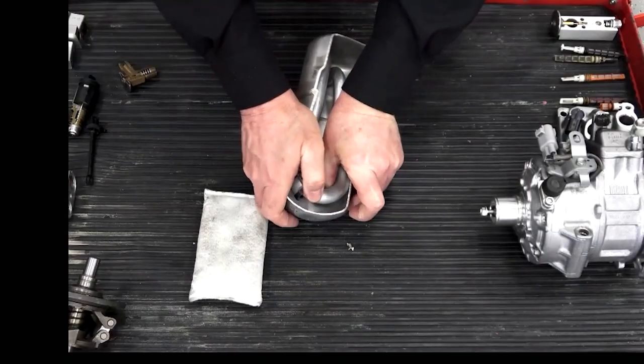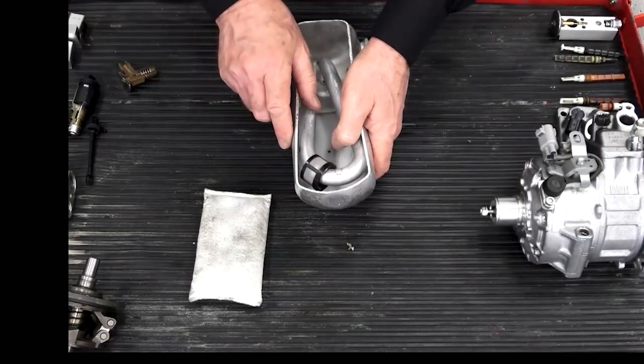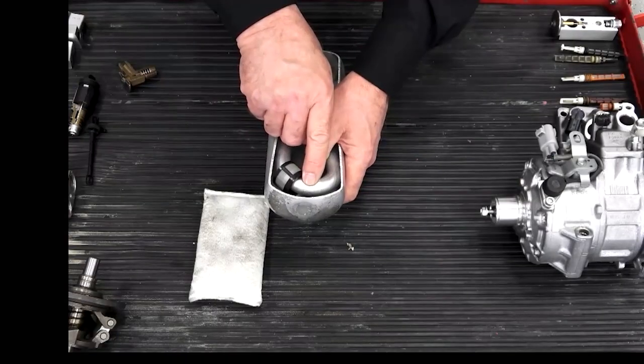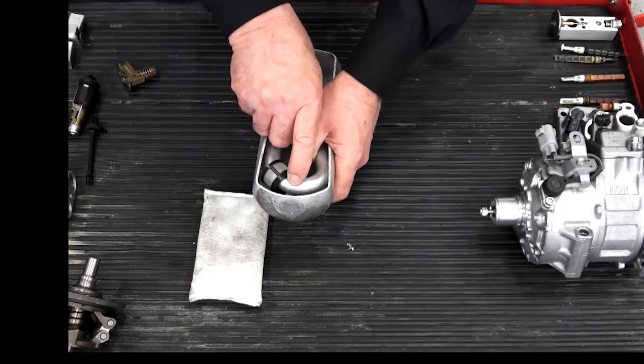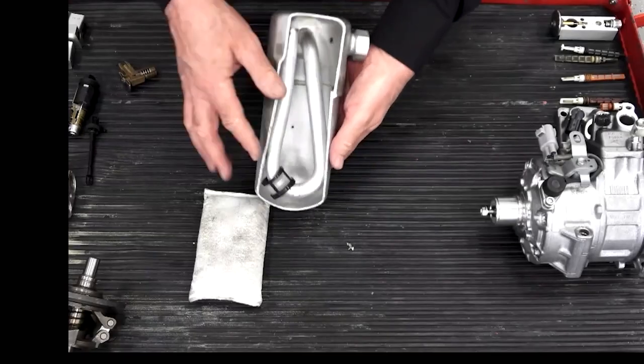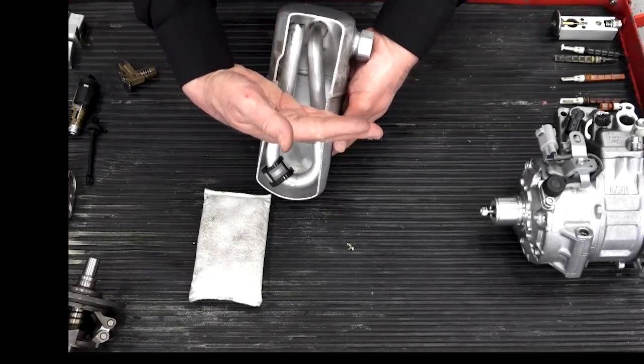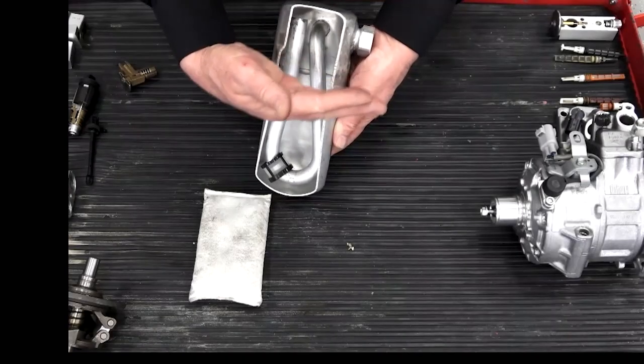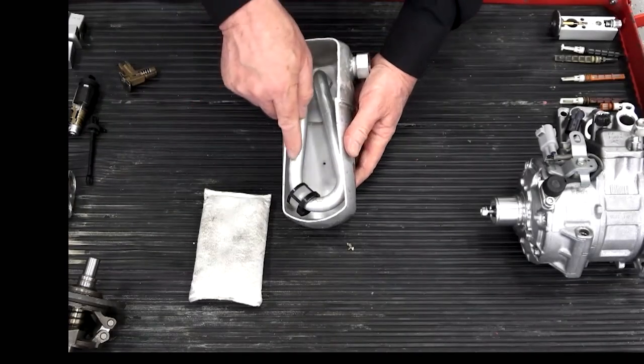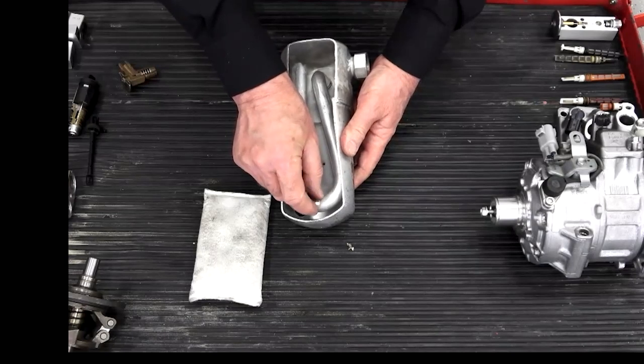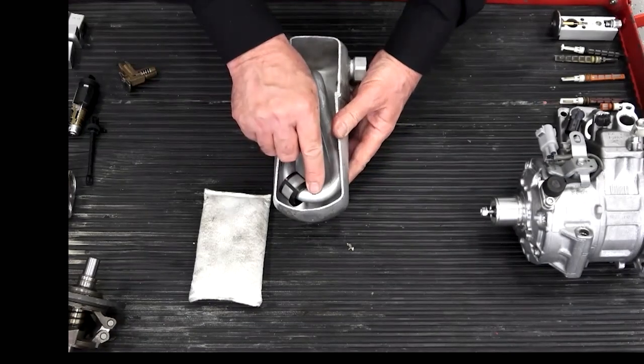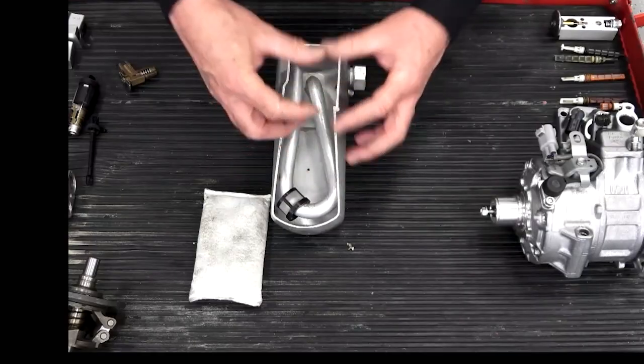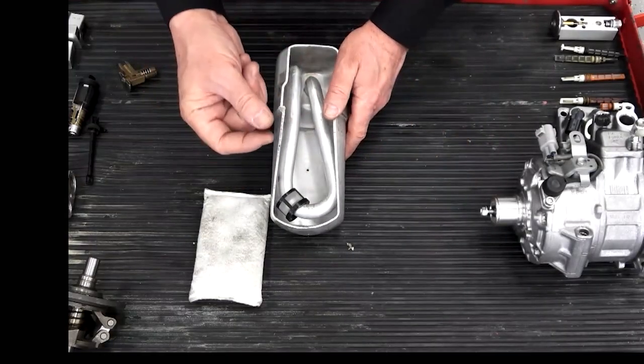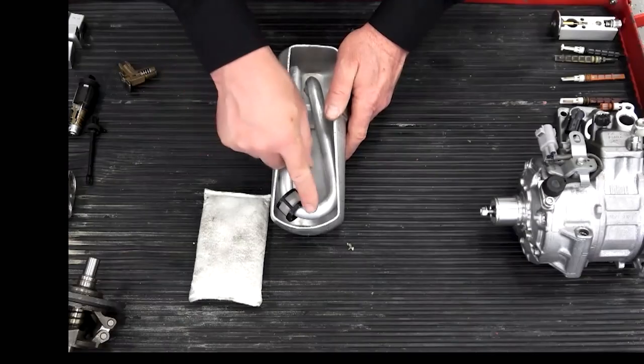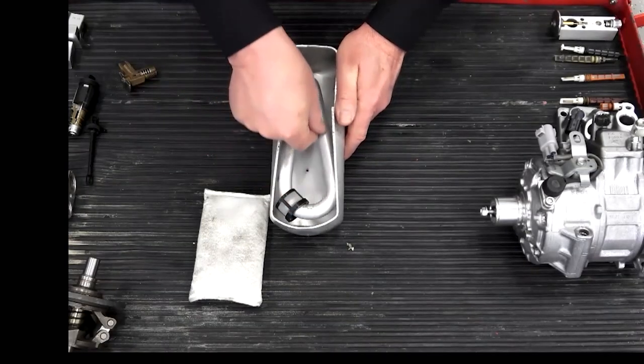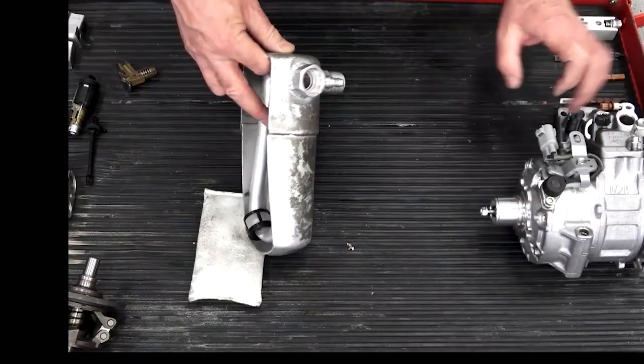And what happens? Do you see there's a little barrel filter here right at the bottom of the J tube? If we look carefully here, you may be able to see it. There's a tiny pinhole in the very bottom of that J tube. And remember, this is very important, this can will be 1/3 to maybe 1/2 full of liquid refrigerant and oil. So as the gas is drawn down the J tube, it creates a low pressure area, a Venturi effect, just above the pinhole. And through that pinhole, we get a fog of oil and refrigerant, micro droplets of refrigerant being drawn through that pinhole and mixed with the gaseous refrigerant being drawn back to the compressor.